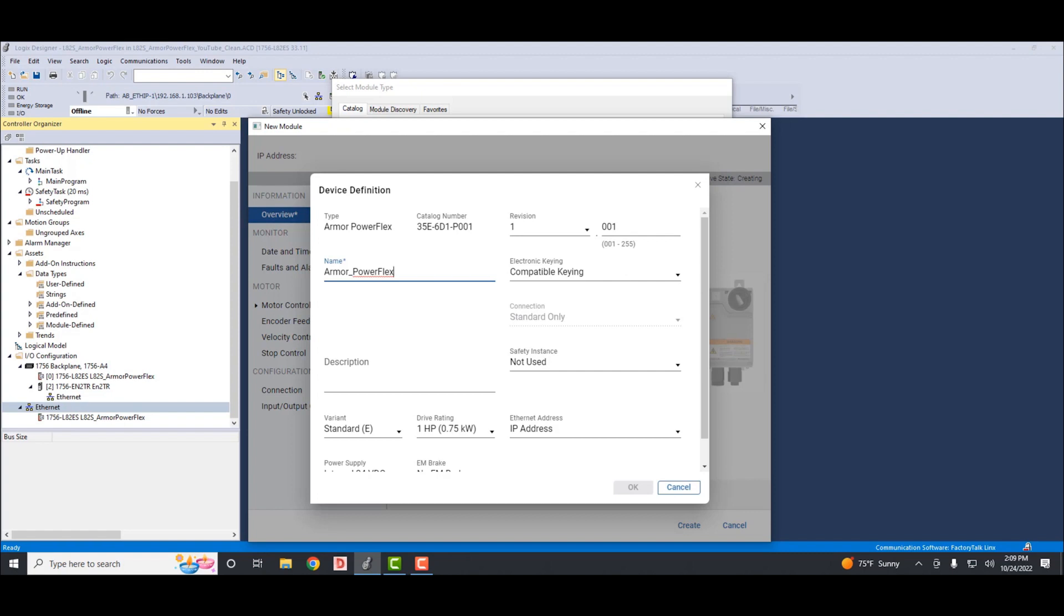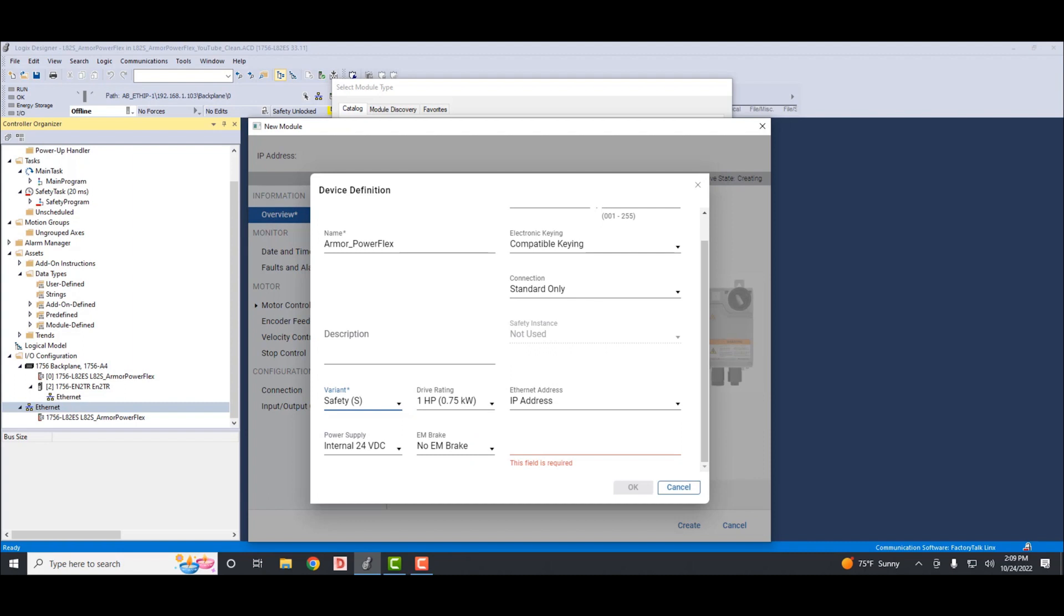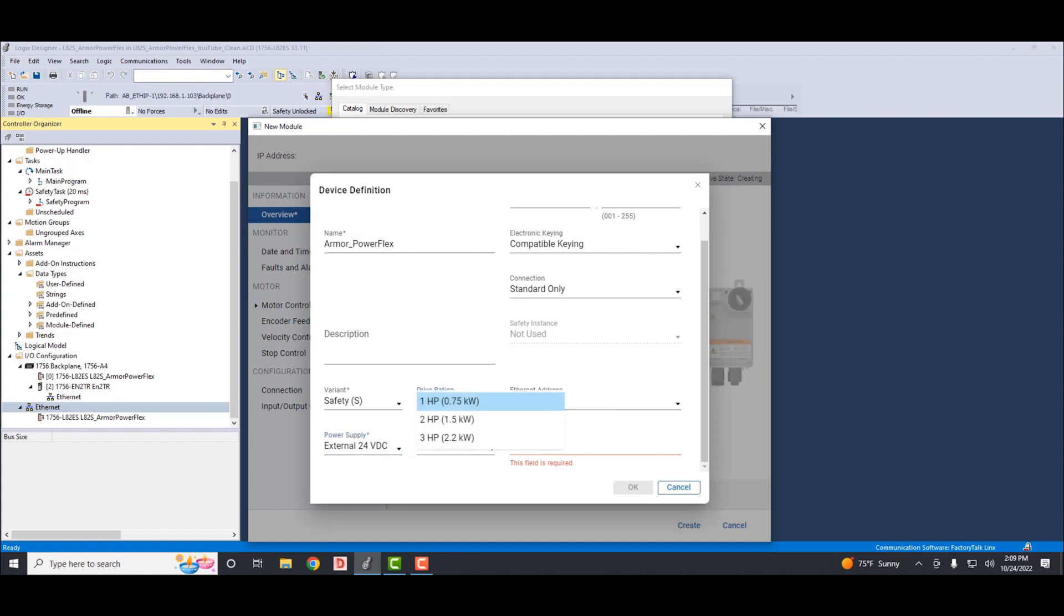Then we'll go down to the variant. It has two options: standard and safety. Our drive is a safety drive, so we'll select safety. Then we'll go to the power supply. Power supply has two options: internal and external. Ours is an external 24-volt DC supply, so we'll select external. Then we'll go to the drive rating. This is where you select the horsepower rating of the drive. Ours is a one horsepower drive.